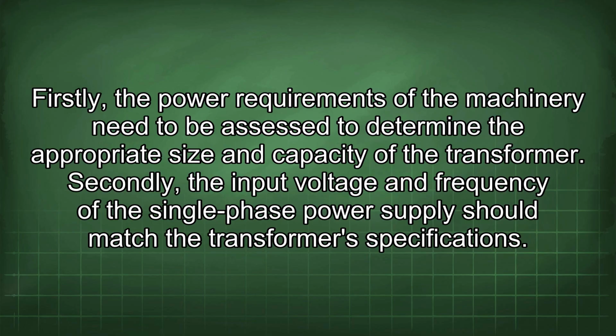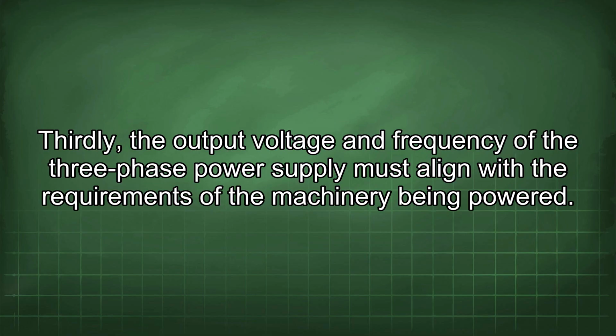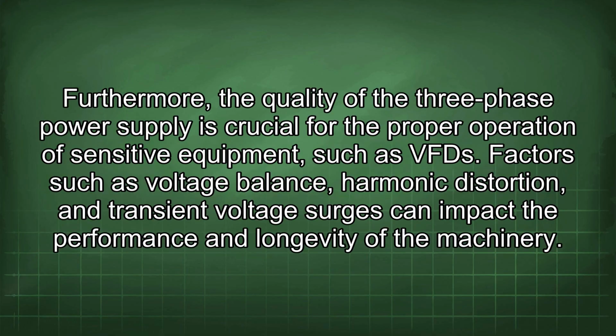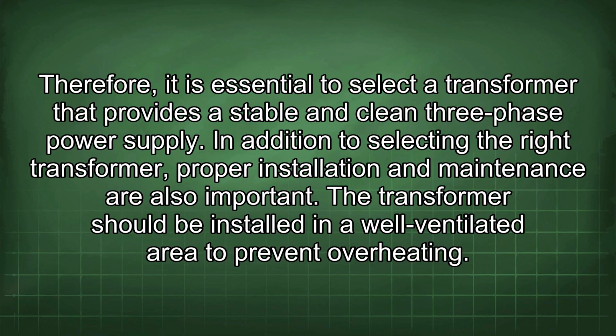Firstly, the power requirements of the machinery need to be assessed to determine the appropriate size and capacity of the transformer. Secondly, the input voltage and frequency of the single-phase power supply should match the transformer specifications. Thirdly, the output voltage and frequency of the three-phase power supply must align with the requirements of the machinery being powered. Furthermore, the quality of the three-phase power supply is crucial for the proper operation of sensitive equipment, such as VFD. Factors such as voltage balance, harmonic distortion, and transient voltage surges can impact the performance and longevity of the machinery. Therefore, it is essential to select a transformer that provides a stable and clean three-phase power supply.